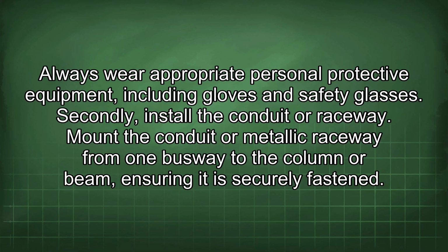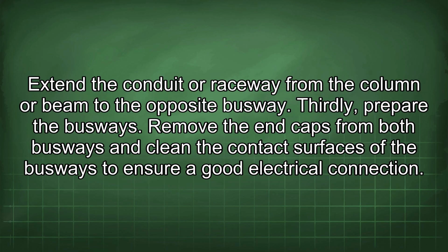Secondly, install the conduit or raceway. Mount the conduit or metallic raceway from one busway to the column or beam, ensuring it is securely fastened. Extend the conduit or raceway from the column or beam to the opposite busway. Thirdly, prepare the busways. Remove the end caps from both busways and clean the contact surfaces of the busways to ensure a good electrical connection.